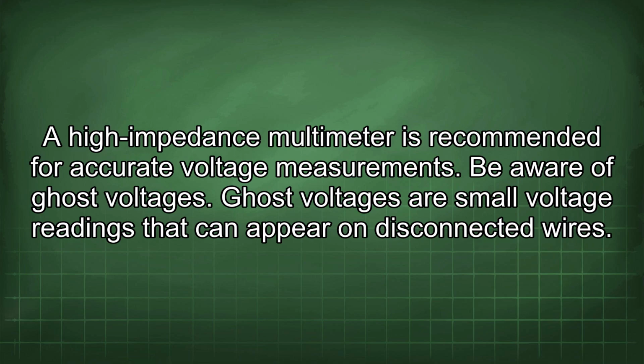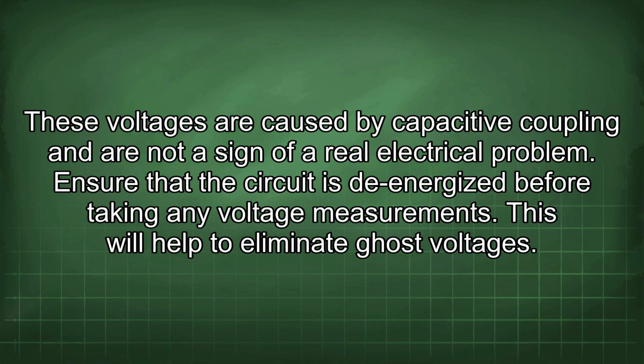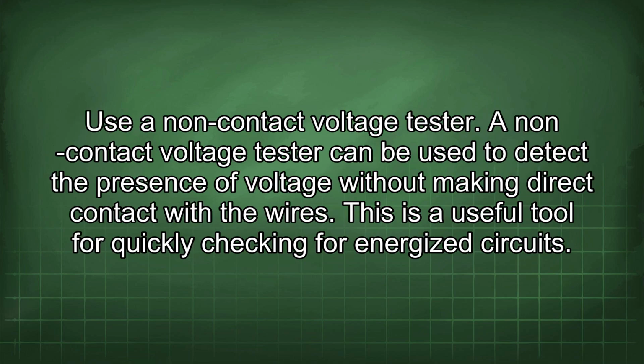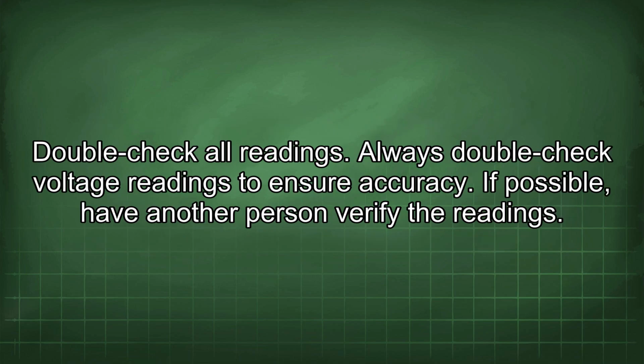Be aware of ghost voltages. Ghost voltages are small voltage readings that can appear on disconnected wires. These voltages are caused by capacitive coupling and are not a sign of a real electrical problem. Ensure that the circuit is de-energized before taking any voltage measurements. This will help to eliminate ghost voltages. Use a non-contact voltage tester. A non-contact voltage tester can be used to detect the presence of voltage without making direct contact with the wires. This is a useful tool for quickly checking for energized circuits. Double-check all readings. Always double-check voltage readings to ensure accuracy. If possible, have another person verify the readings.